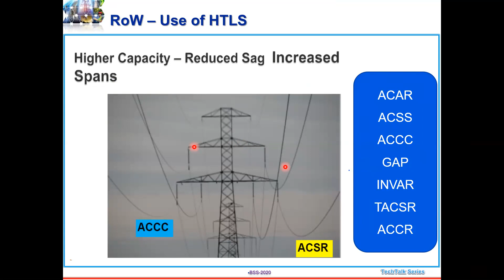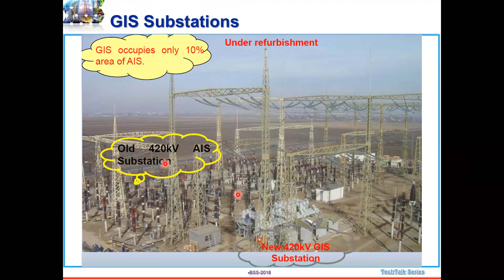When you see GIS, this is actually a 400 by 220 kV substation where the GIS was introduced. What happened was, after the introduction of GIS, you had this much spacing. Only the whole substation will come down like this. So that's the main attraction. Your footprint comes down like anything when you go in for GIS. Of course, it will be at a cost, but still the cost has come down like anything.